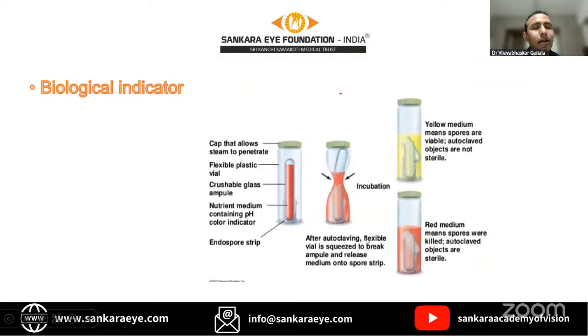And the third one is the biological indicator, which is the gold standard of all. It is a flexible plastic vial. Inside there is a glass ampoule with medium, and outside there is a spore strip. This spore strip contains Geobacillus stearothermophilus bacteria, which is highly resistant to heat. You should keep this vial along with the load.